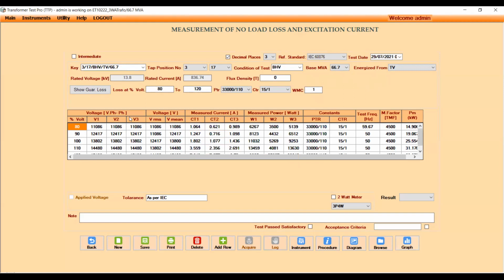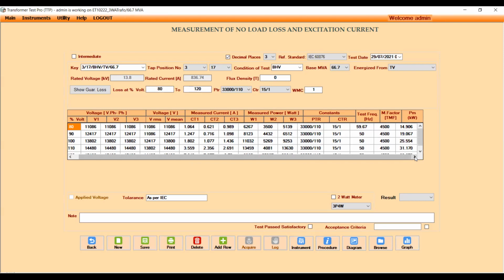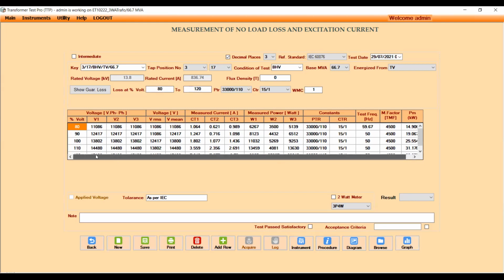And then how do you conduct the no load loss test? In the case of a completely automated system, the voltage rises to the rated voltage and the measurements are taken in this particular table and get populated automatically. That completely automatic setup we have built up to 1.5 MVA, 1500 kVA. It can go up to the 36 kV class.